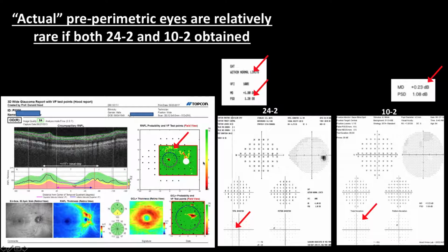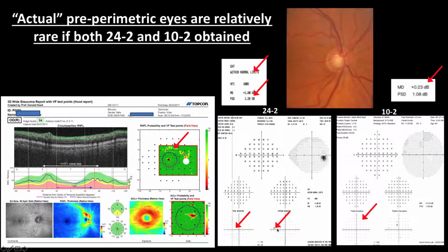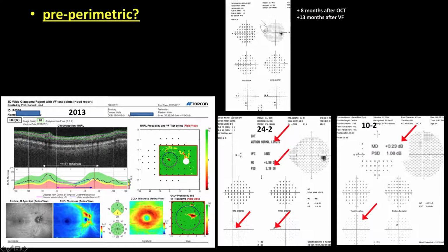There's something going on here. I believe it's real because you can see it here and you can see it down here. That point probably is real, but you would never believe it based on only this evidence. You can see the damage up here too as well on this photo. Right? Here it is down here on the thickness map.